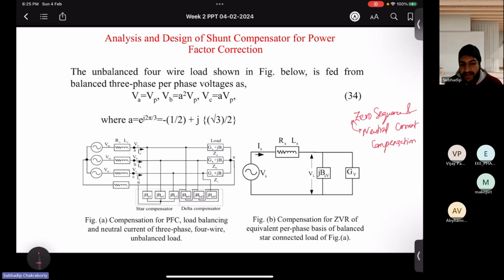But what type of compensator can provide it? Neutral current compensation. Who can provide? Can delta type compensators provide or star type compensators provide? Anyone? Yes, because star has already a neutral branch that can be connected to the neutral of the supply. So always remember, for neutral current or zero sequence compensation, you need star kind of compensators. And what will be the delta and star doing together then? So we have divided the roles among the compensators. That star will be doing the power factor correction and neutral current compensation. These are philosophies. If you do like this, then the compensator values will come down. So star will be responsible for zero sequence or neutral current compensation as well as power factor regulation. What will delta do?